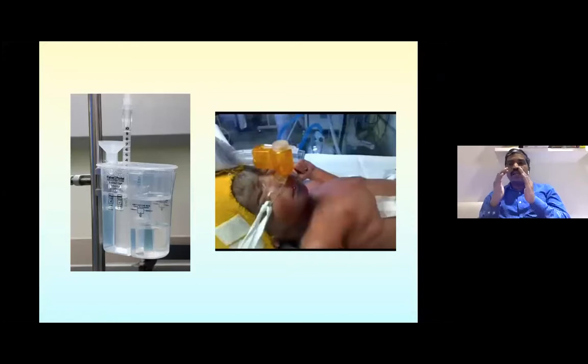So to increase the pressure going to the patient, you push this tube inside so that from the water level, the tube is 6 centimeter inside. You want to decrease the pressure, you pull this tube outside so that from the water level, the tube immersion depth decreases. So whatever is displayed here, if it is 4 centimeter here, it means from the water level, the tube is 4 centimeter inside. When you push it, if it becomes 5, from the water level, it is 5 centimeters. So this is what is generating the pressure in bubble CPAP.